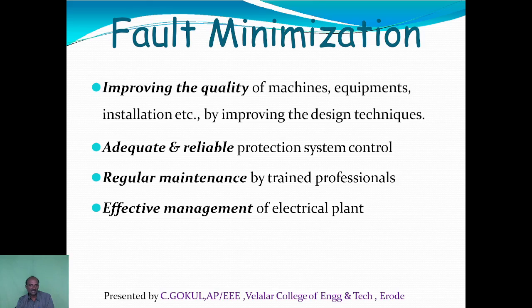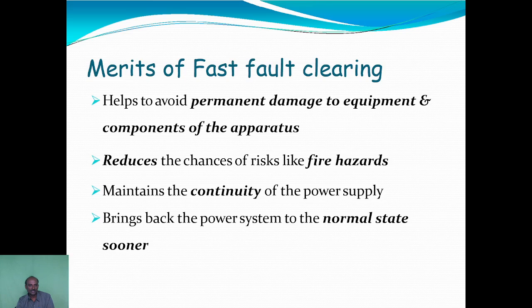Fault minimization. By improving the quality of machines, equipment, installation, and also by improving the design techniques, we can minimize the fault levels. Adequate and reliable protection system control. By using protective systems, we can minimize the faults, along with maintenance and effective management. Merits of fast fault clearing: it avoids permanent damage to equipments, reduces the chances of risk, maintains continuity of the power supply, and also brings the power system back to the normal state sooner.